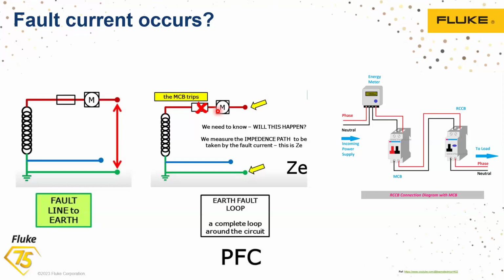It can definitely cause the protective devices to operate slowly or not at all, resulting in failure of fault detection. This definitely puts the system at risk, and over a period of time it can easily lead to damage. So we have to measure and verify the earth fault loop impedance regularly. This is an important part of electrical system testing and regular maintenance, to ensure proper protection and safety.